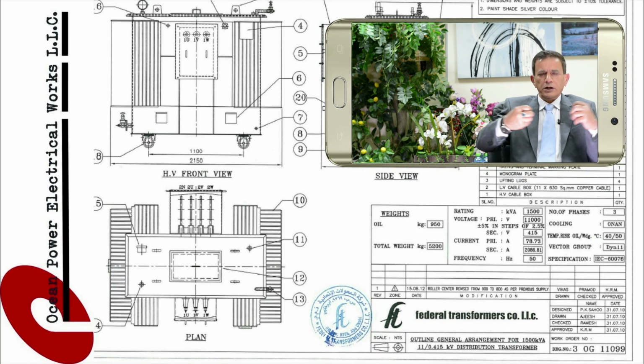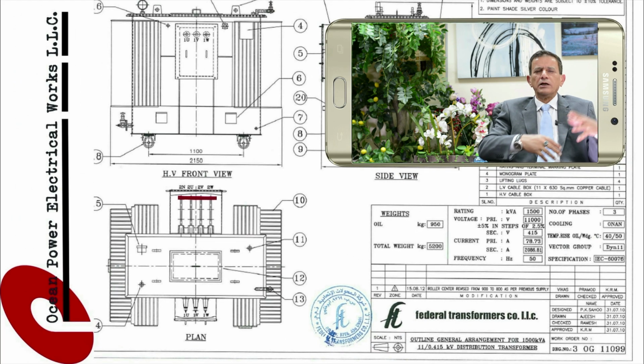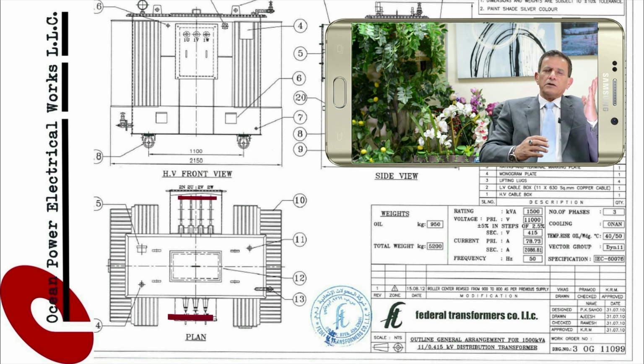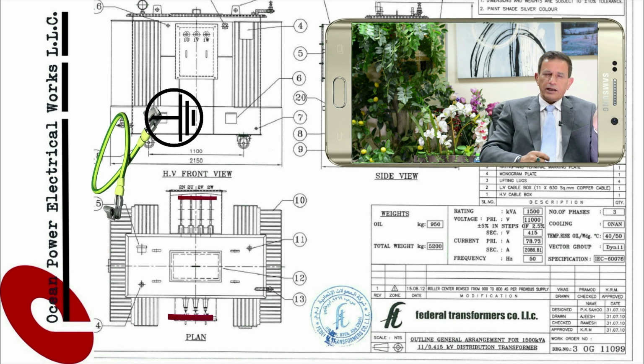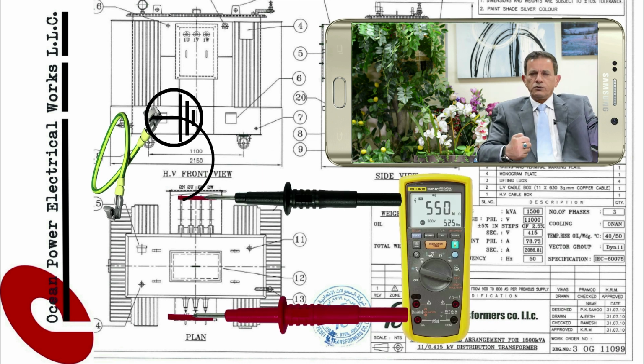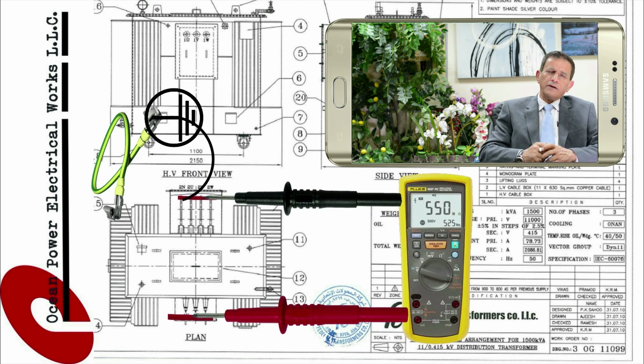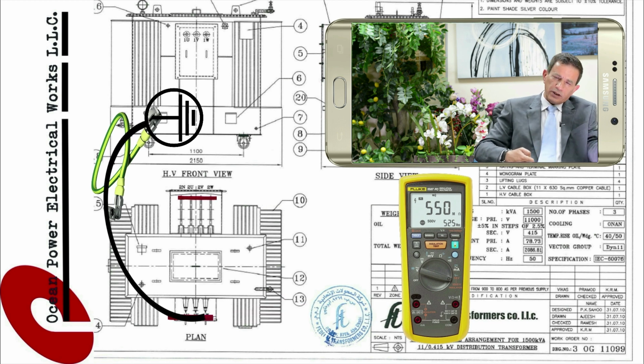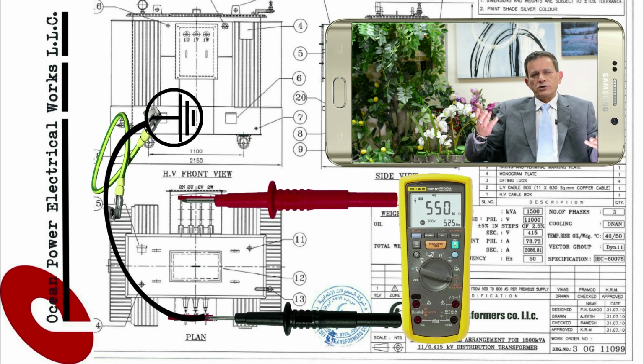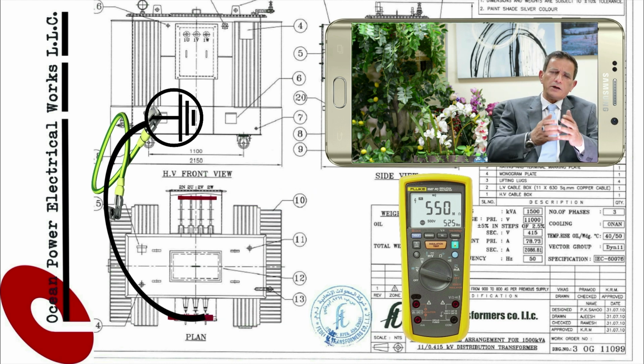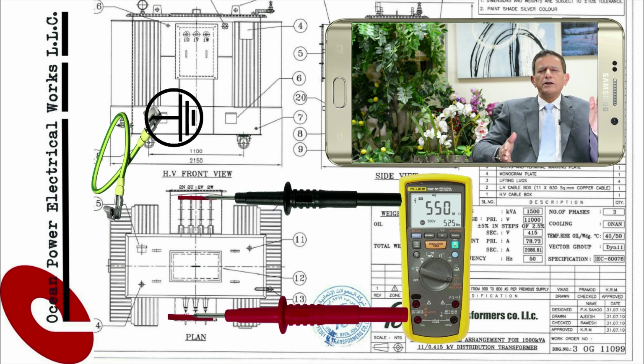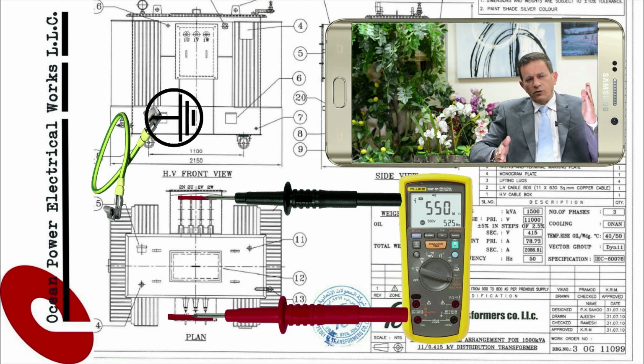So after connecting the LV terminals together and the high voltage terminals together, one time we'll connect the low voltage terminals to the earth and measure the insulation resistance between the high voltage and earth. Next time we'll connect the high voltage side to the earth and measure the insulation level between the low voltage and earth.